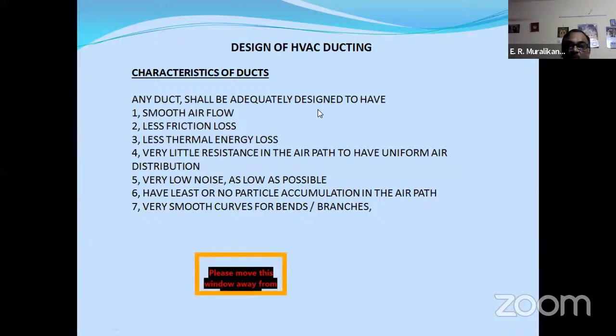Any duct shall be adequately designed to have smooth airflow, less friction loss, less energy loss, very little resistance in the air path, uniform air distribution, very low noise, as low as possible, least or no particle accumulation in the air path, and very smooth curves for bends and branches. We are not going to talk about geometry or fabrication details, such as the angle or the radius of curvature, because those are covered by separate standards, and SMACNA defines all those requirements. We'll be talking only from the energy point of view: if you have proper ducting, what will be the energy saving potential?